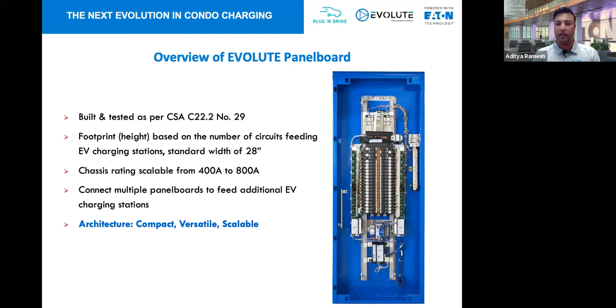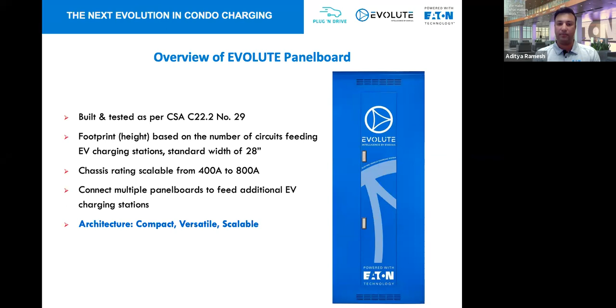You can have multiple panels forming a larger grid for additional EV loads. So a 400 amp panel can do 20 EV chargers, and an 800 amp can go all the way up to 30 EV chargers. You can have multiple panel boards and scale the total number of parking spots in your building that are managed on the same network in that fashion.